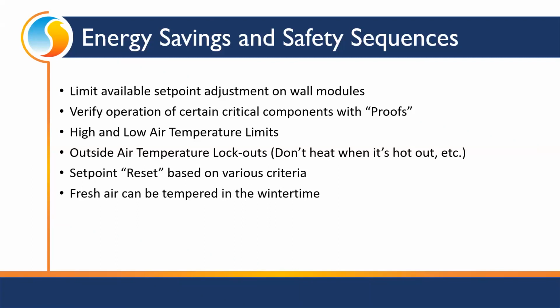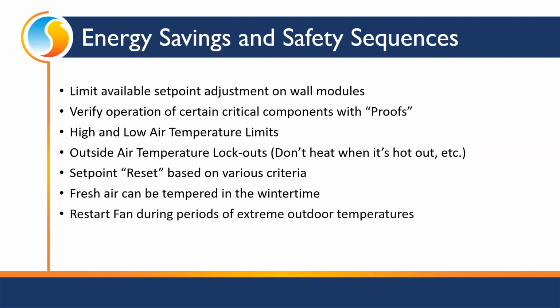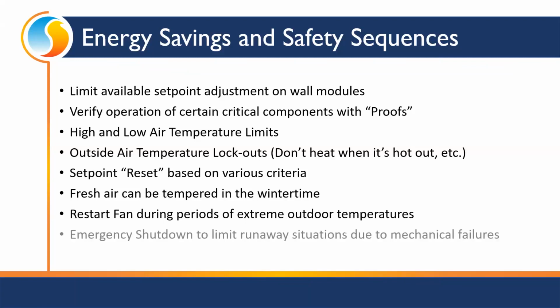So back to that demand controlled ventilation, a perfect example is a church Sunday morning in the middle of January. Everybody's in there breathing out their CO2. We start opening the dampers, but we're bringing in really cold air. Well, we can bring on some heat to just take the chill off of that air. Okay, we can restart the fan during periods of extreme outdoor temperatures. If it's super hot or super cold outside, we're going to turn the fan on just to keep things moving, make sure we're not getting any cold spots in the corners, possibility of freezing, that kind of stuff.